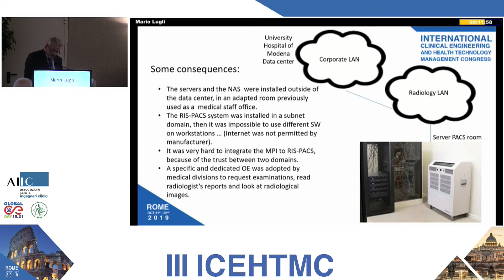We can say that the safety of this RIS-PACS installation was not high because the server room was 1 meter under the road surface, inside the MRI building, near the MRI rooms. Split ceiling cooling was installed in the server room and sometimes caused water to leak onto servers. And there was no redundancy on the power supply, and we used only UPS to guarantee electrical continuity.